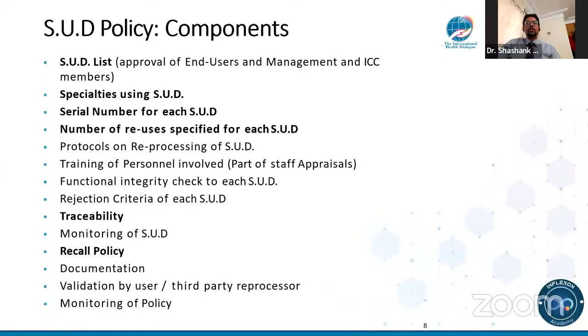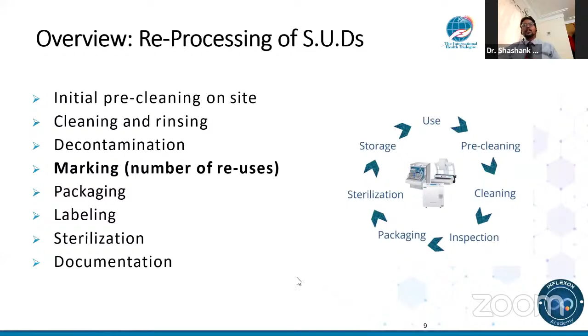So if you look at the reprocessing of single-use devices, on your left-hand side, you would see the typical steps. On the right-hand side, you would see the cycle which is followed for the sterilization of most regular reuse devices that you see in the CSSD. But one of the key differences that you will see is a marking that we will do in terms of how these reuse devices are handled. We will go to a few slides later when we talk about the marking and how you do the labeling and understand how they're being reused. I think that is something that we'll look at in a couple of slides. Can we have the next slide, please?